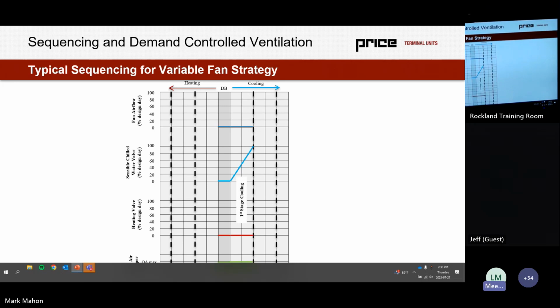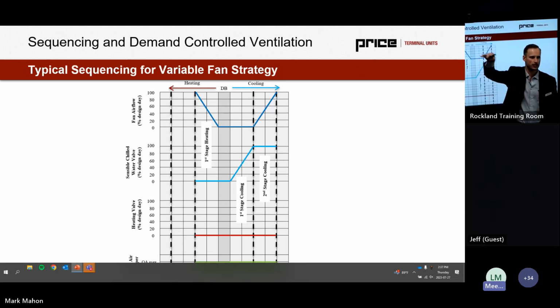When the space does get too hot, we're going to need to cool it down, and the way we do that first is hydronics, typically for this kind of product. The reason for that is if we look at the first stage of heating, the first thing we do is air. The rationale is the zone is probably stratified, the ceiling is going to be a little bit warmer. So if we increase our fan energy and mix more air down into the space, that air is probably a degree or two warmer, and it's going to make the space more comfortable.